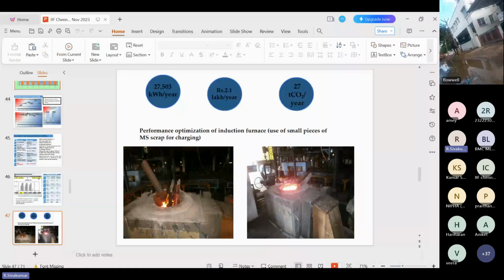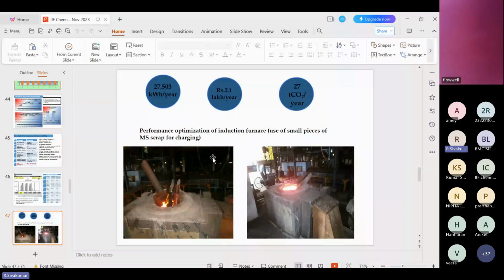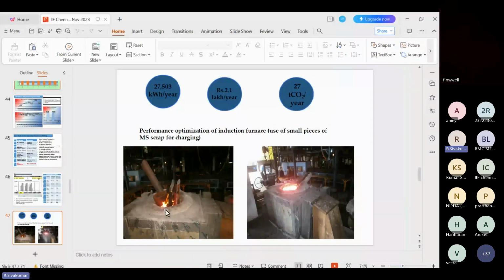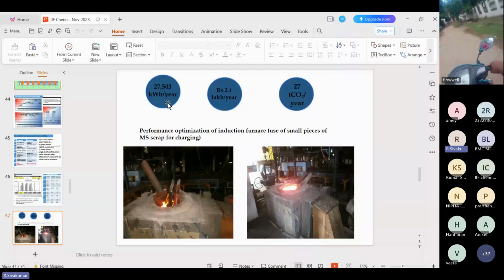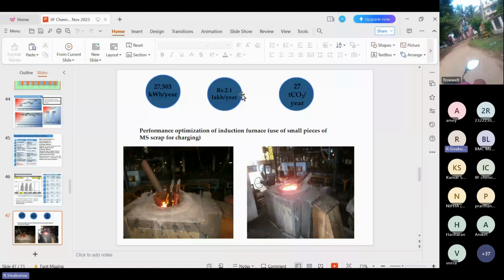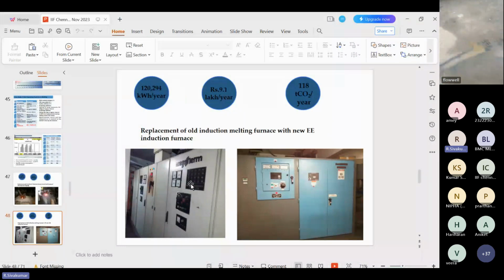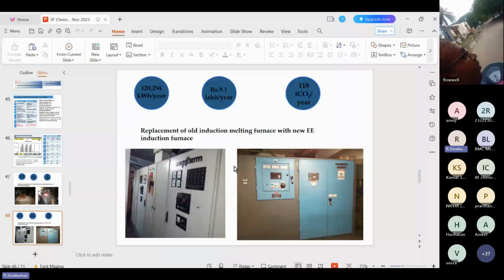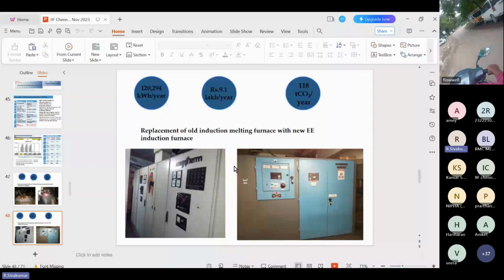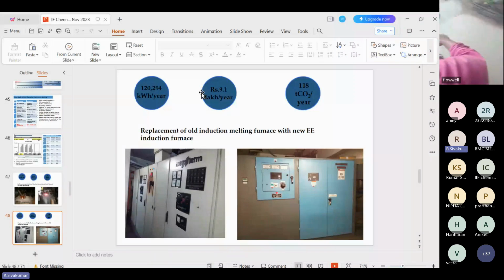Some of these practices are taken from TERI, because TERI, a Delhi-based company, worked with our Coimbatore cluster. We are sharing the same with you foundrymen also. By performance optimization of the induction furnace, by charging small pieces of MS scrap, they saved nearly 27,503 units in a year, and 2.1 lakh rupees, and 27 tons of CO2 emissions were reduced. Similarly, replacing the old furnace with energy efficient induction furnaces. Nowadays IGBT models are also available. It gives a minimum of 7 to 8% energy savings over the existing one. So here 1,20,294 units were saved, 9.3 lakhs cost was saved, and 118 tons of CO2 emission was reduced.